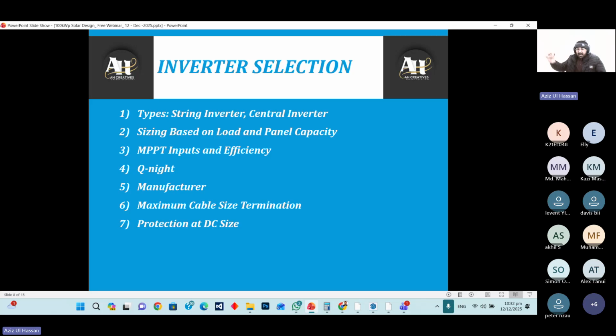Basically, the large-scale inverters, like the string and central inverters, have the capacity for kVAr generation. So at nighttime, when the grid is on, we have to provide kVAr production from the inverters. Some string inverters will not generate that power, but the central inverter has a Q at night functionality.